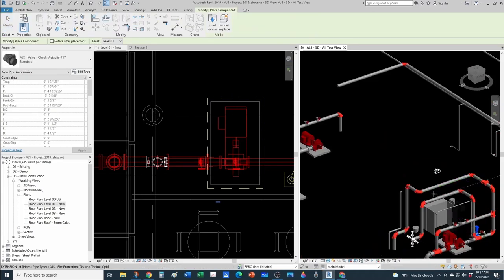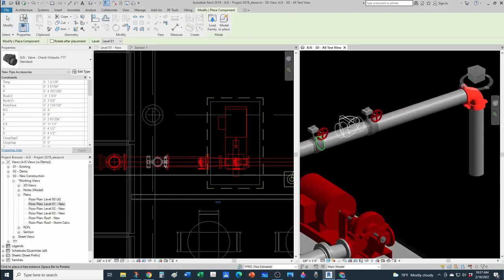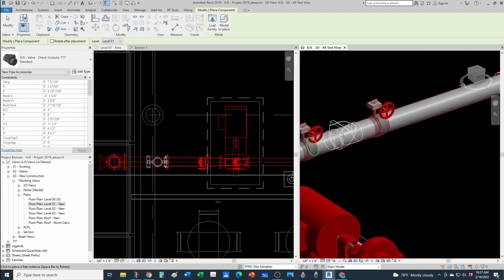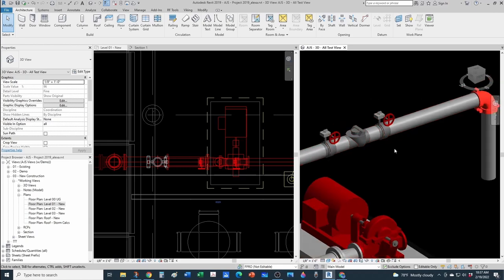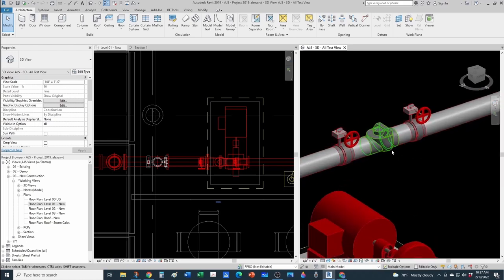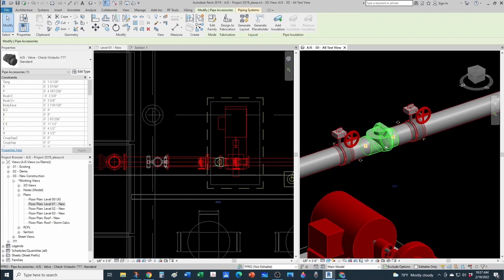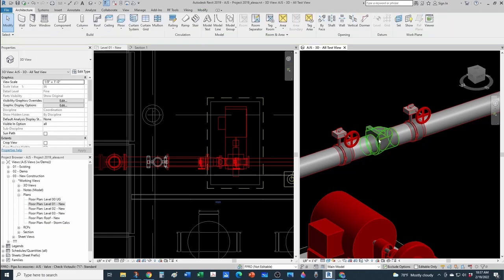So I'm going to provide a check valve here. I'm doing also create similar, and again, all this content is available at the Victaulic website. They're really good. You can also use Tyco, Viking, whatever manufacturer you use, as long as they have the BIM models. You can see that this check valve came in the wrong way. If you see the cut sheet and you see a cut through it, you'll see that the check valve would be oriented the wrong way. So this is the correct way of orienting it, like this.